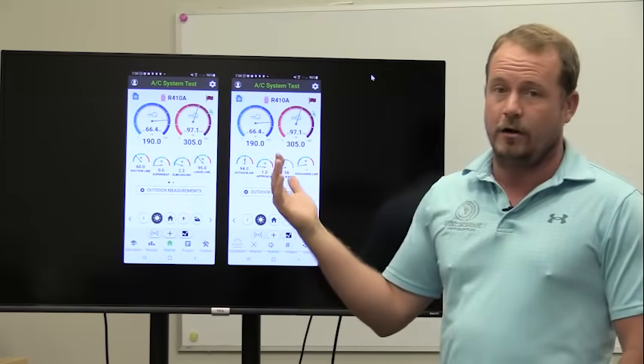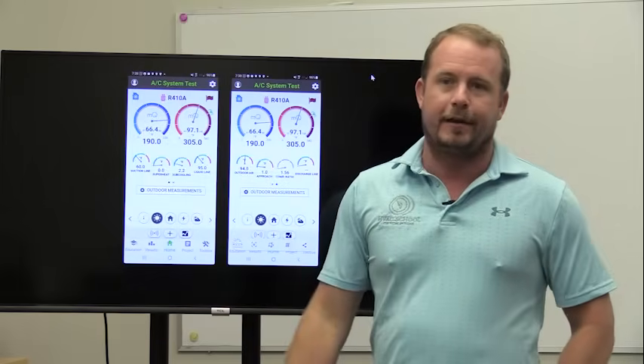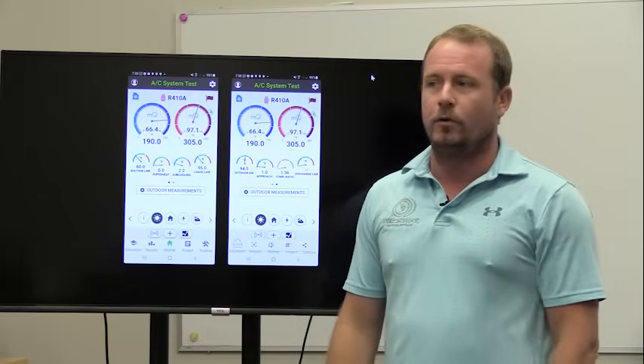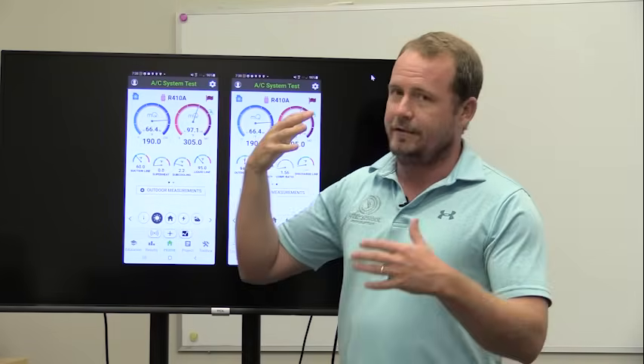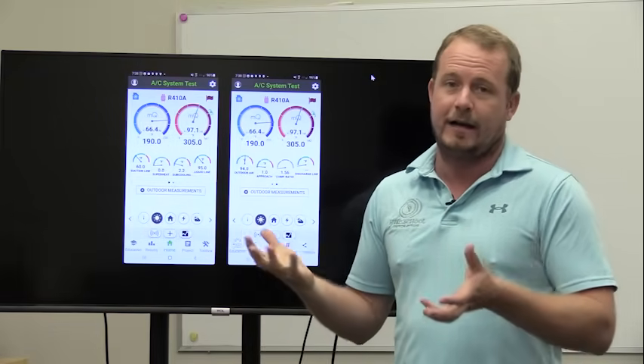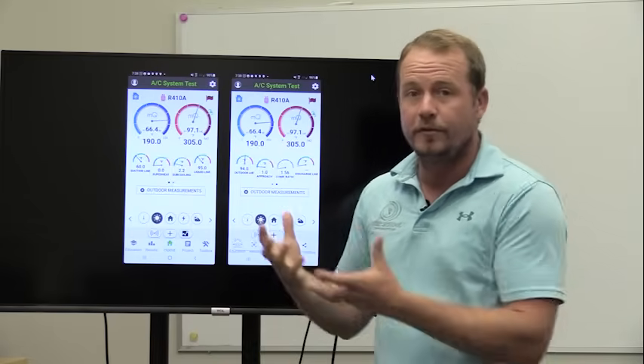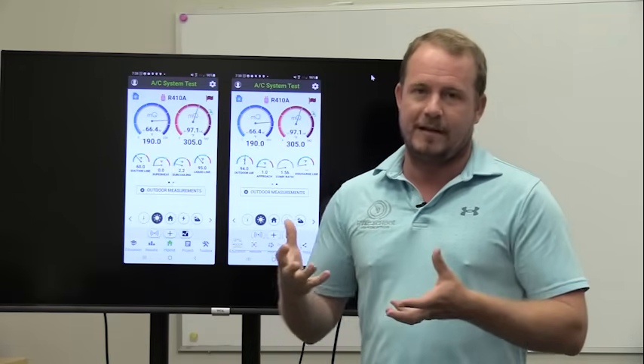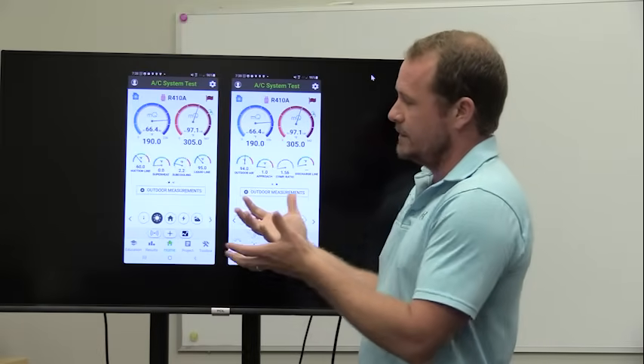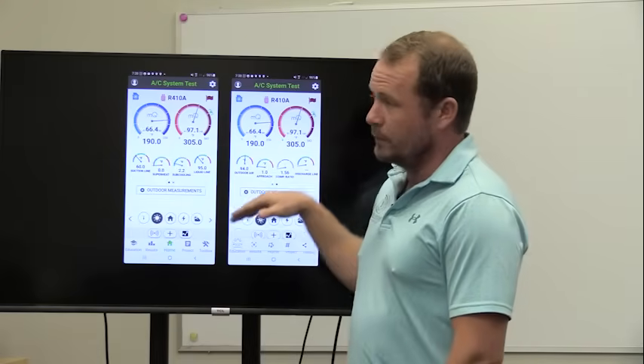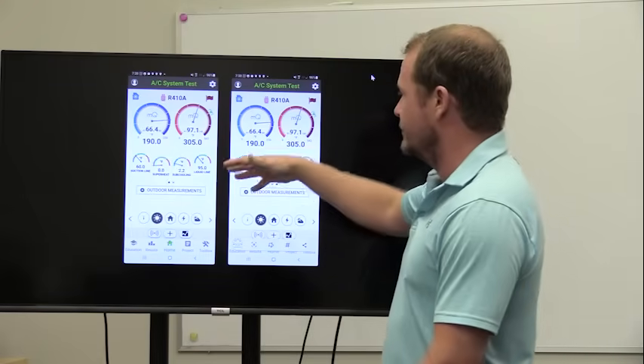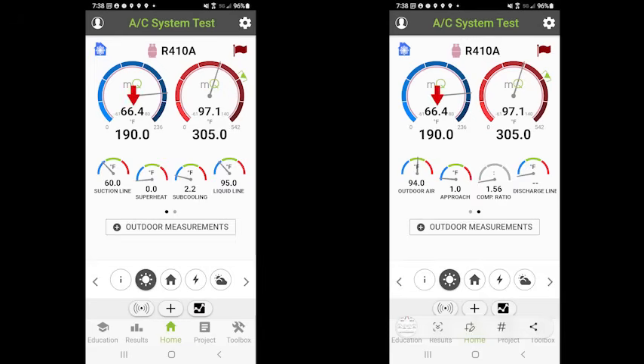And higher compression ratio for no reason, just because you've got a dirty condenser or somebody keeps their AC really cold inside, that's not a good thing. We don't want higher compression ratios than we need, because if you have a high compression ratio, that means high current system's not going to run as efficiently. It's not going to move as much refrigerant because of mass flow rate being reduced. And mostly that has to do with lighter suction gas returning to the compressor. But we also don't want compression ratios this low, because then we have the circumstances that we're seeing here, got a 66 degree evaporator coil. The compressor, we're relying on it to move refrigerant. That's its job. So if it's not pumping, that can be a problem.